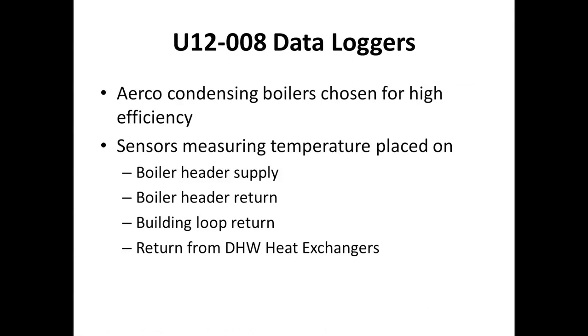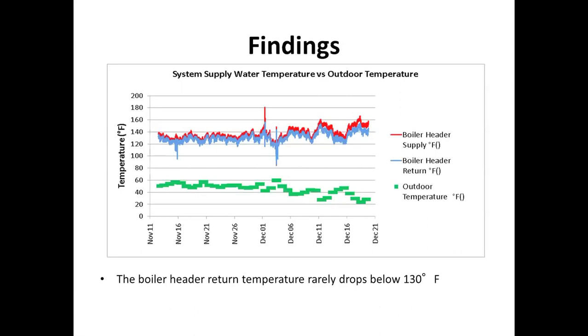The U12008 data loggers we used to really evaluate a building that had Aerco condensing boilers installed that were chosen specifically for high efficiency, yet utility bills were still extremely high. So we went in there to test out the building and see how we could use data loggers to verify whether the unit was performing as expected or not as expected. We placed temperature sensors at the boiler header, supply and return, the building return, and also the return from the domestic hot water heat exchangers.